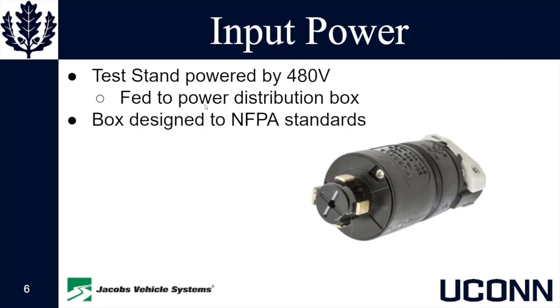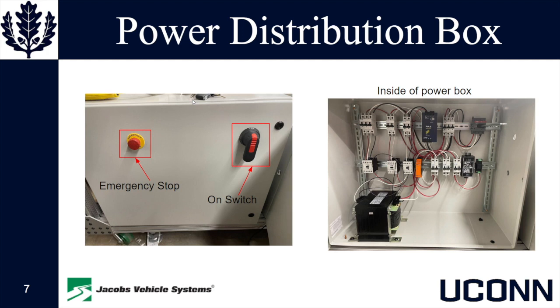The power distribution box is fed with 480 volts, and for safety, we have designed the test stand with NFPA standards. Here are the inside and outside of the power distribution box. The red button on the left side is our emergency stop function, which cuts power to the entire stand in case of an emergency. The disconnect switch is located to the right of the emergency stop. Its purpose is to cut power when the box is opened.